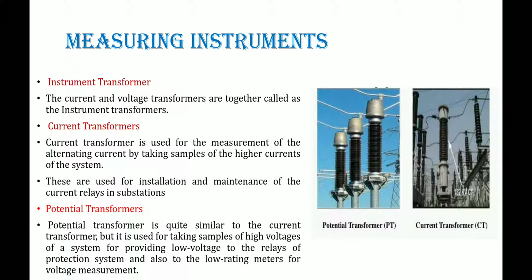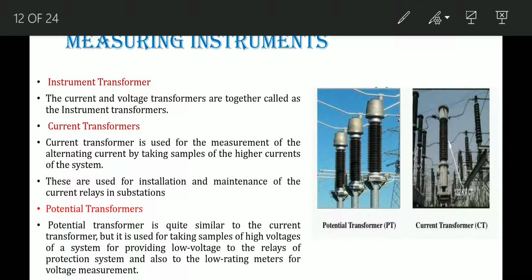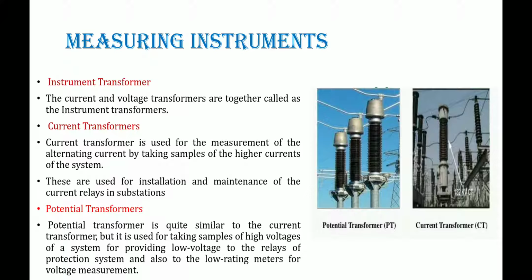The potential transformer, similar to the current transformer, is used for measuring higher voltages by taking samples of the high voltages of the system, to provide low voltage to the relays of the protection system and to low-rating meters for voltage measurement.